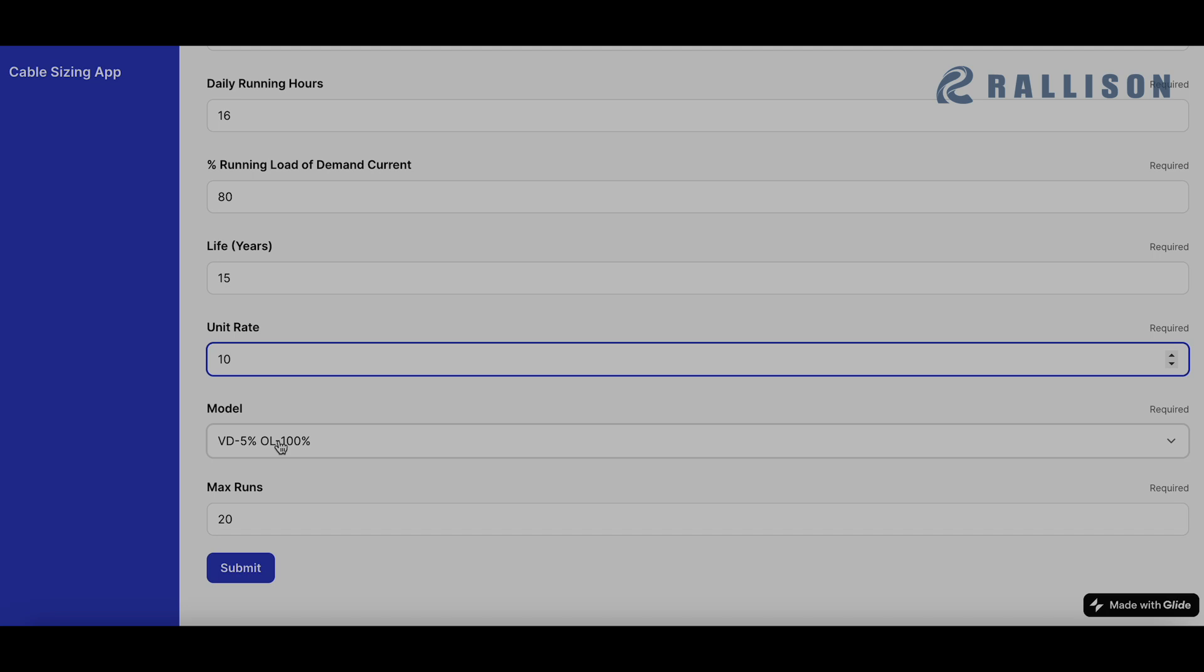VD 5% means that the maximum permissible voltage drop for the design is 5% and OL 100% means that we are designing or selecting the cable size based on the current rating of the cable at 100% of the demand current, obviously adjusting for the derating factors.